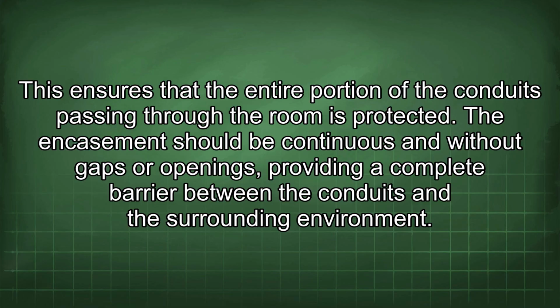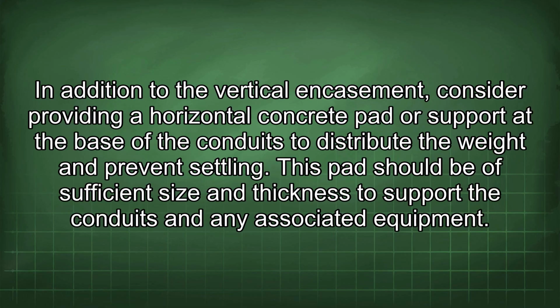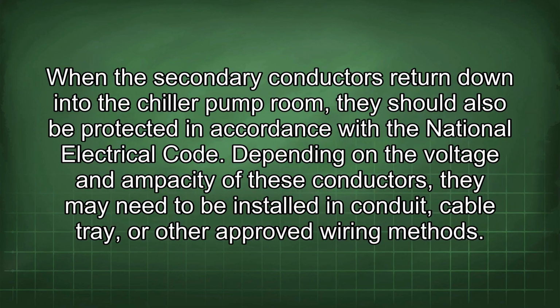The encasement should be continuous and without gaps or openings, providing a complete barrier between the conduits and the surrounding environment. In addition to the vertical encasement, consider providing a horizontal concrete pad or support at the base of the conduits to distribute the weight and prevent settling. This pad should be of sufficient size and thickness to support the conduits and any associated equipment. When the secondary conductors return down into the chiller pump room, they should also be protected in accordance with the National Electrical Code. Depending on the voltage and ampacity of these conductors, they may need to be installed in conduit, cable tray, or other approved wiring methods.